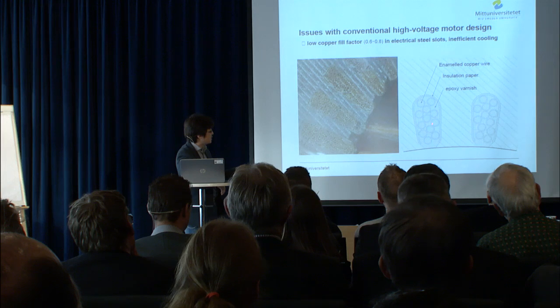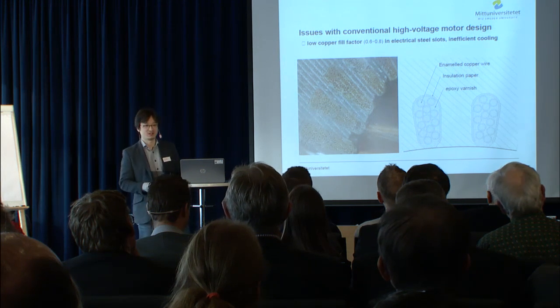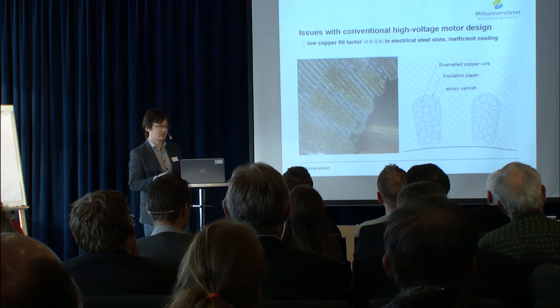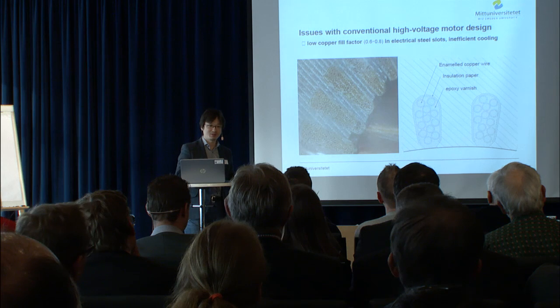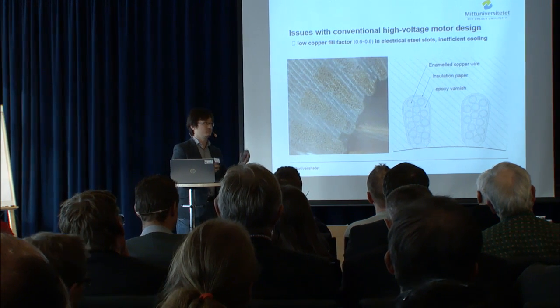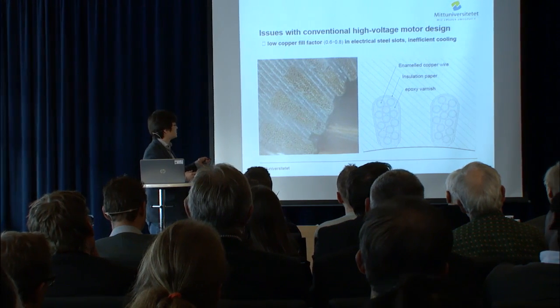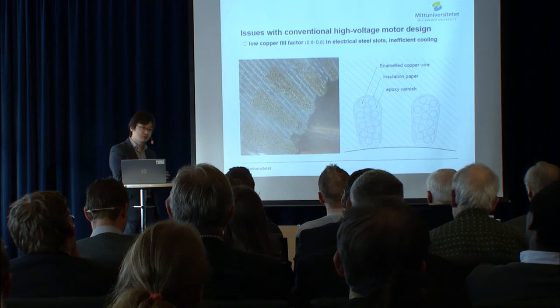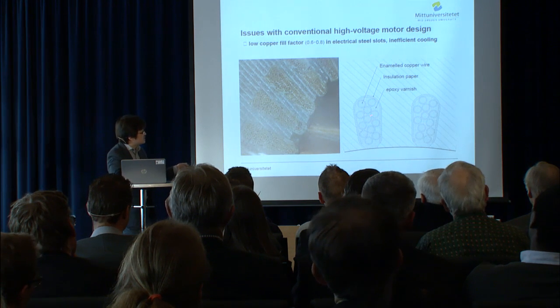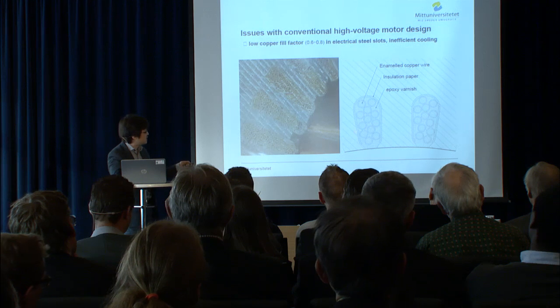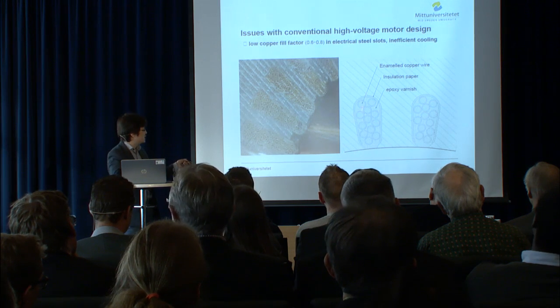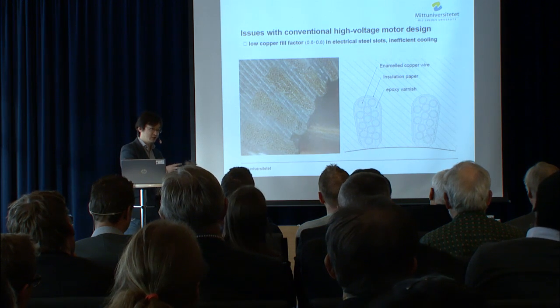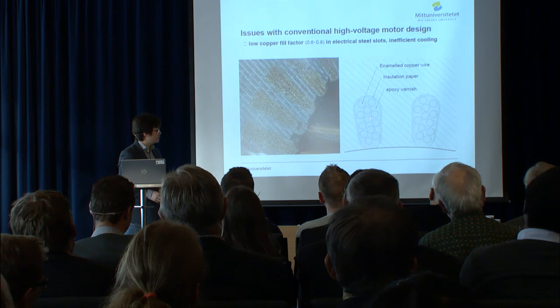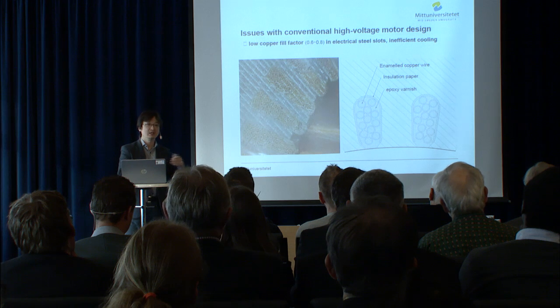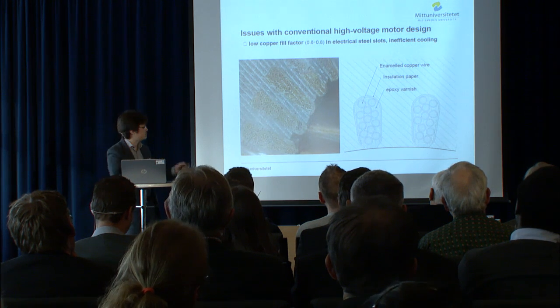And all these voids, all this empty space, is filled with varnish, epoxy varnish. They need to get it solid, sturdy, with no dirt and dust coming in. But all these materials are super bad at conducting heat. Actually, the major reason you can break an electric motor is by overheating. So heat loss, and also this bad thermal conduction, is going to be a major issue. It's always the center wire which gets the hottest, with electrical steel around it, and you have no other way to cool this center point. It's always the hottest. So this limits the maximum power, maximum torque, the highest current density the individual wire can take, and also limits the lifetime. If it's too hot, it wears out, it damages the insulation, short circuits happen, it's bad.